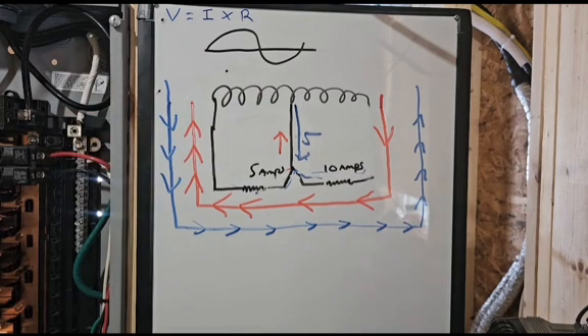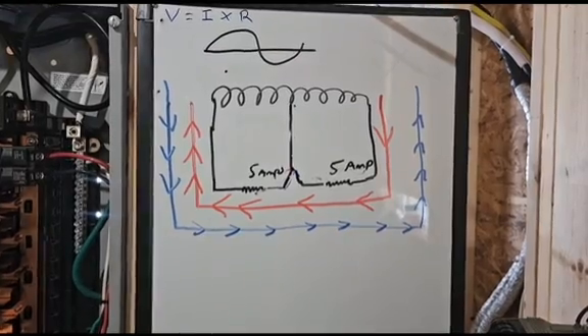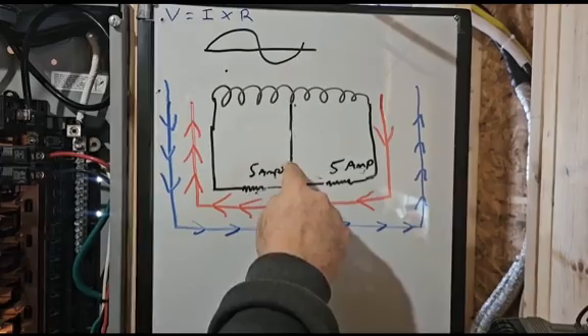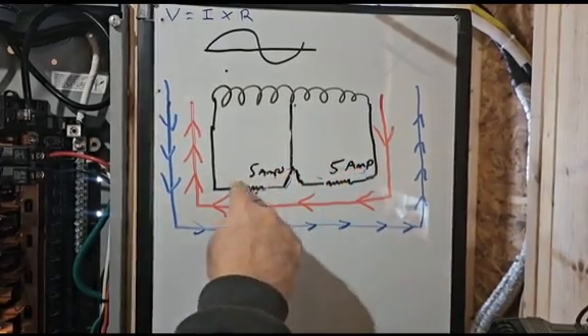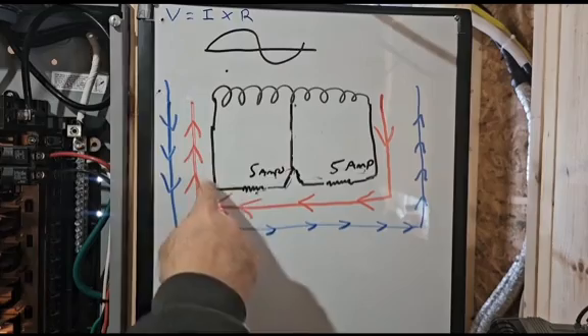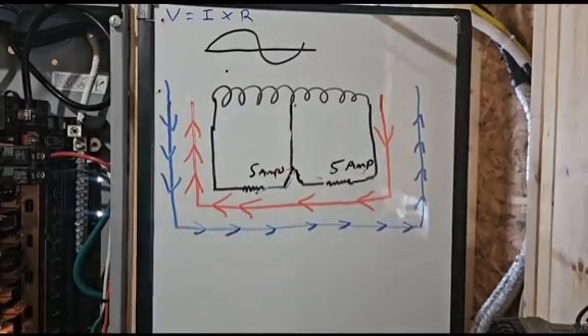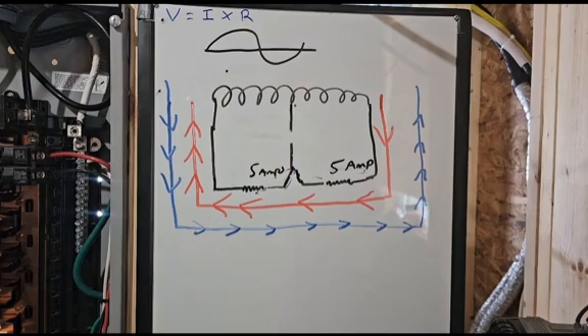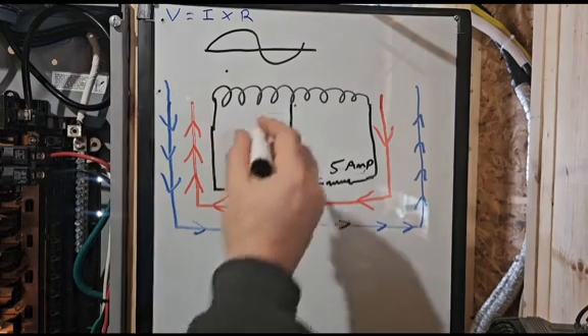Now what happens when it's balanced? When it's balanced on red, we have 5 amps coming this way. Ohm's Law calls for this one to be 5 amps as well, so the same 5 amps continues through and back to the transformer. When we're blue, this 5 amps goes that way and the neutral is irrelevant. You could even remove it and everything would function just fine.